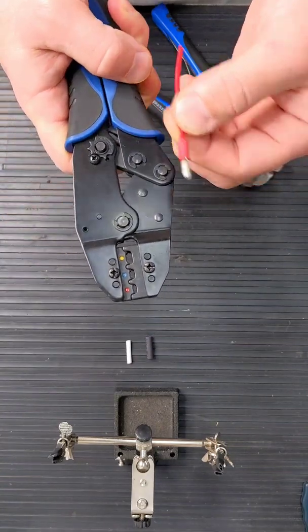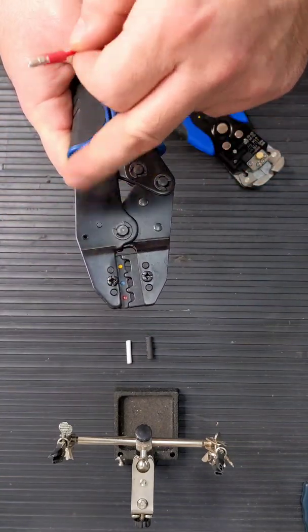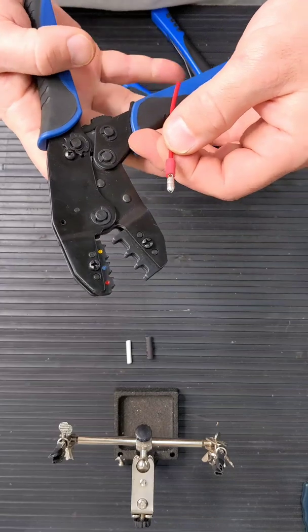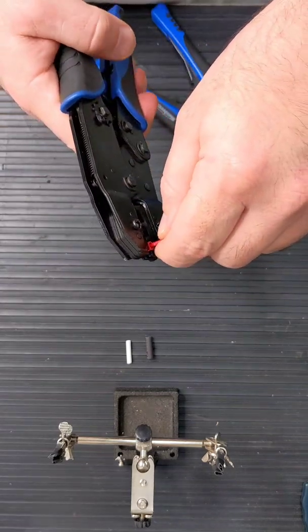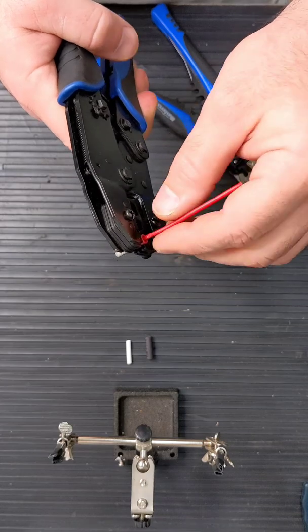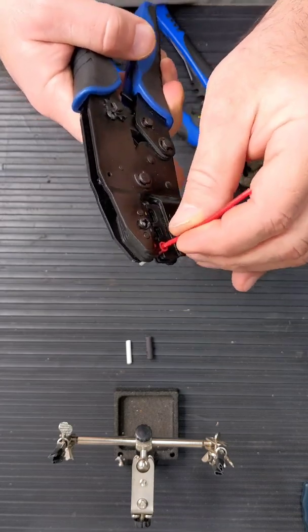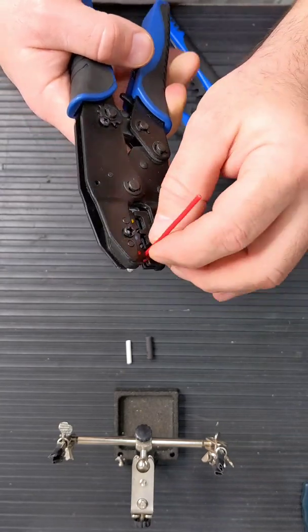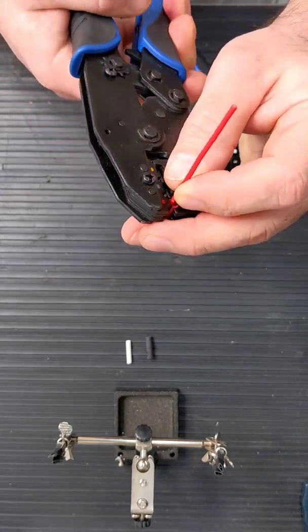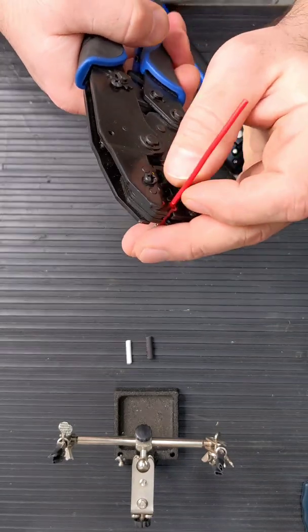You want to get your crimper and use the corresponding color. Red would be for the red connector. Place it in there and tighten it slightly, but don't crimp it. This way you can push on it to ensure that the wire is fully within the connector, and then crimp.